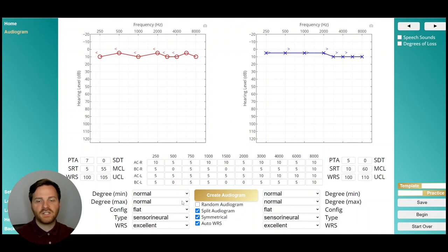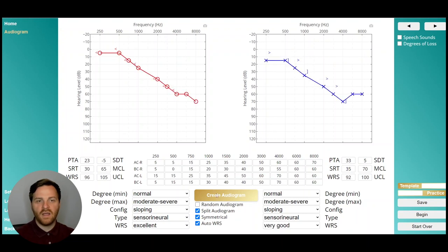If you check symmetrical, any changes made to one side will be applied to the other. This can save you some clicks when designing your audiogram, so that you can make a normal to moderately severe sloping hearing loss in one ear and it will apply those same settings to the other ear.